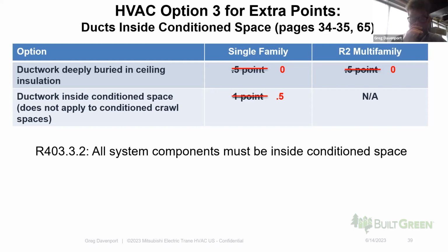By the book in the code, all system components must be inside conditioned space. So that means your air handler. So if you're using a central heat pump, that should be inside conditioned space. Mostly around the Seattle area, we see people doing that. There are some jurisdictions where they're a little more flexible and they're still putting them in the garage. Technically, that's not the way it should be in Washington.